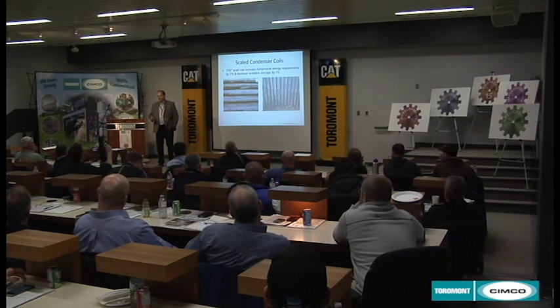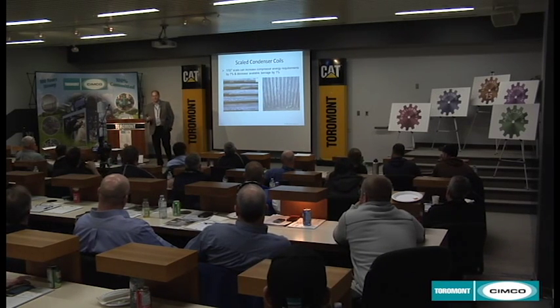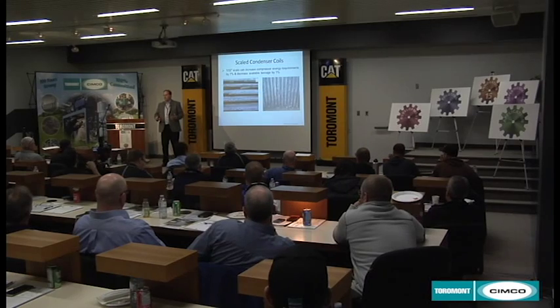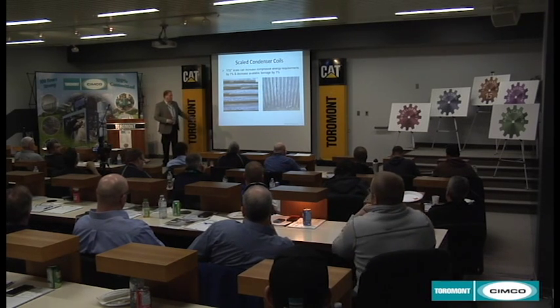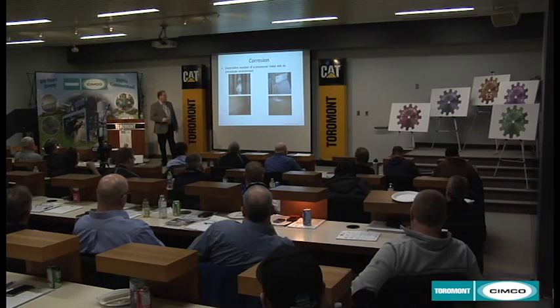It's not a lot. I always tell people, if you want to compare what scale does, get yourself an eggshell, put your finger inside the eggshell, and light a match underneath it. Do you feel the heat? No. Take the eggshell out, light a match under your finger, and you'll feel the heat really fast. Eggshell is scale. Scale is an insulator, which covers your condenser pipes and causes that energy increase. That's what water treatment helps you prevent: it keeps those condenser tubes clean.